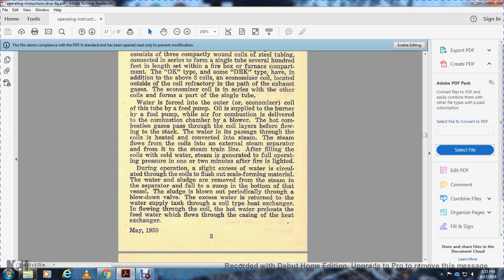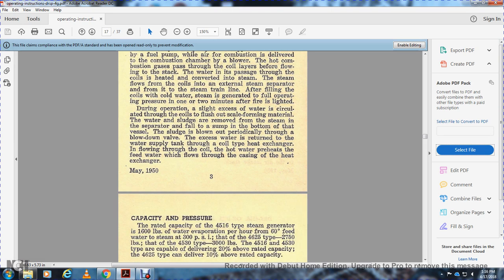During operation, the slightly excessive water circulation through the coil flushes out scale-forming material. The water sludge is removed from the steam and separated by falling into the sump at the bottom of the vessel. Sludge is blown out periodically through a blowdown valve. The excess water is returned to the water supply tank through the coil type heat exchanger. Hot water preheats the feed water flowing through the casing of the heat exchanger.